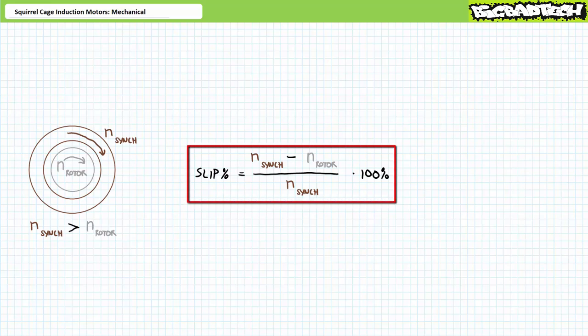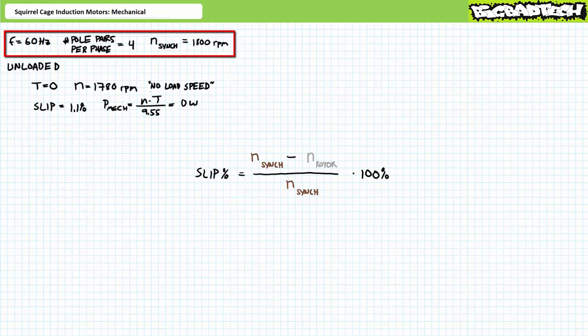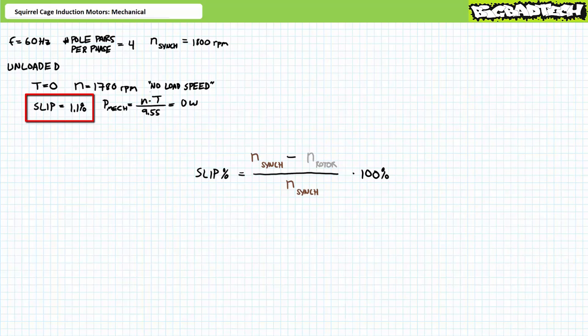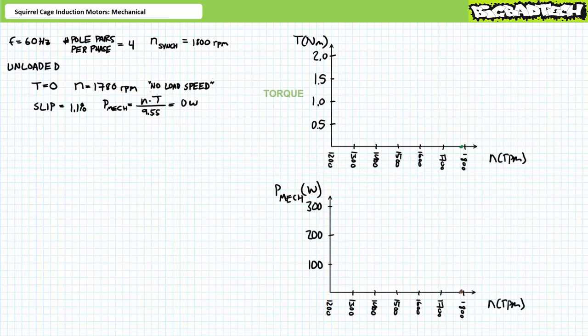This degree of lag is called slip and is typically expressed as a percentage of synchronous speed: percentage slip = (synchronous speed − rotor speed) / synchronous speed × 100%. Consider a squirrel cage induction motor with a synchronous speed of 1,800 RPM. In the unloaded condition, let's say the rotor turns at 1,780 RPM — this is the no-load speed. The rotor lags synchronous speed by 20 RPM, roughly 1.1% slip. In the unloaded condition, the rotor spins quickly but exerts no torque, and the mechanical power formula demonstrates the motor produces no mechanical power.